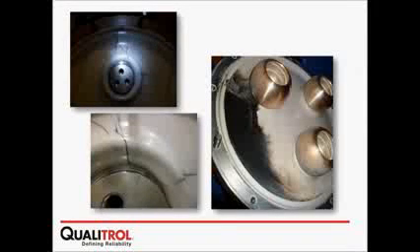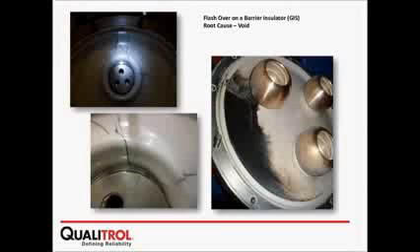I want to show you some good pictures of failures that could not be prevented since they didn't use partial discharge monitoring, and that was caused by a void. So imagine how much work it was to remove this barrier from the GIS. Everything is compact, everything takes time.